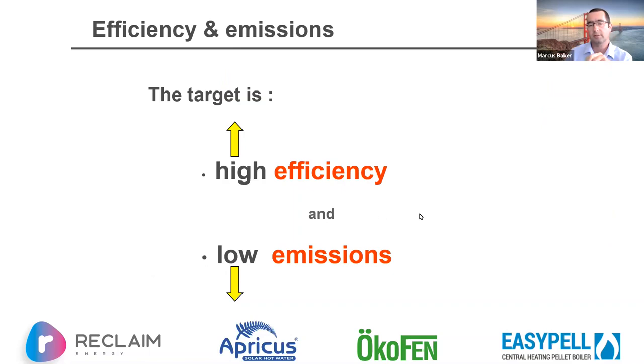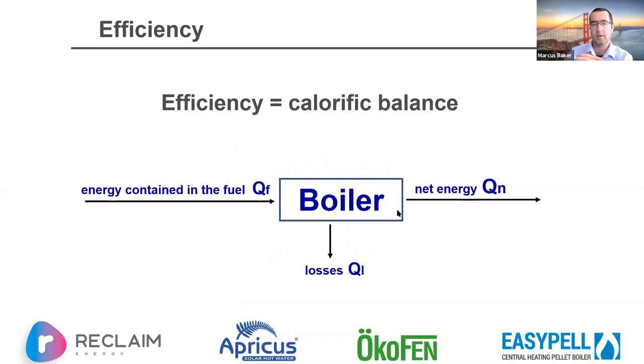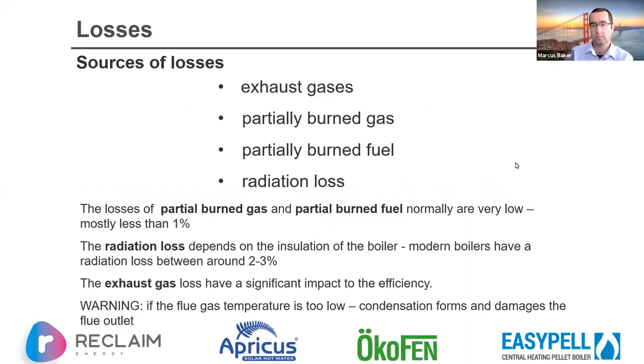The ultimate target is high efficiency and low emissions. Efficiency is measured by the calorific balance: how much energy is in the fuel minus the losses against the energy gain into the water. We lose energy through exhaust gases, through partially burnt gas and fuel, and through radiative losses. In an Ökofen context, partial burning is very low — less than one percent.